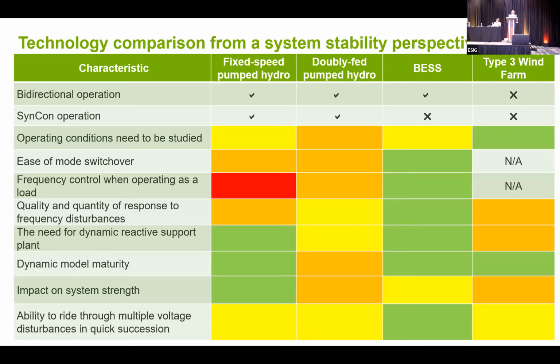This is only from a stability standpoint. Obviously, if you're talking about ongoing supply, these devices, whether fixed speed or doubly fed pump hydro, are superior. But I'm only focusing on stability functions. One of the main differences between battery and doubly fed pump hydro, both power electronic based devices, is the speed of response and flexibility, not needing to switch between modes to provide frequency response. That's by far superior.